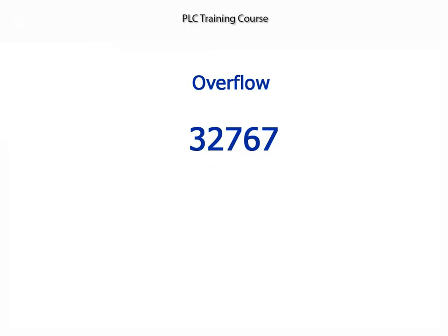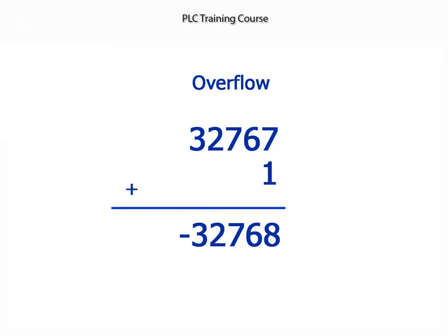Previously, the way PLC stores numbers was discussed. In particular, signed integers were discussed. When a PLC has a number that has gone above 32,767, then the number is treated as a negative number. This could be catastrophic if the number is being used for controlling a process. The jump to a negative number could cause a problem.